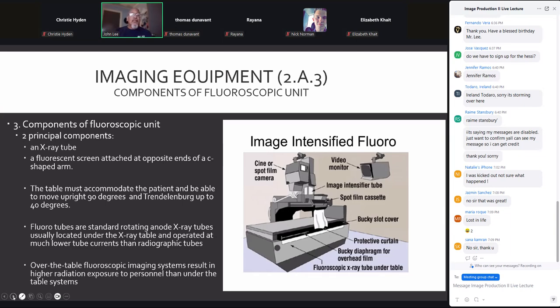So for fluoro units, again, we've got to have an X-ray tube, and then we have to have a special type of image receptor. Most of the systems are going to digital flat panels or CCD type systems or CMOS systems. But the point is, they're going away from the image intensified fluoro. The image intensified fluoro takes the x-rays that are coming out of the patient and converts them multiple times so that we get a very, very bright image at the end of the image intensifier. Now, it is a fluorescent screen that is used in the image intensifiers.